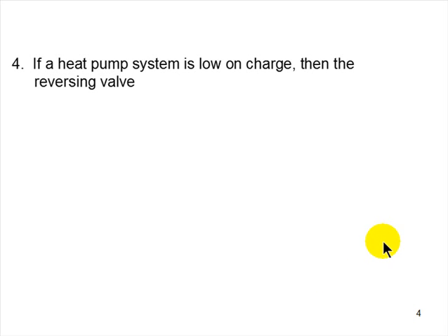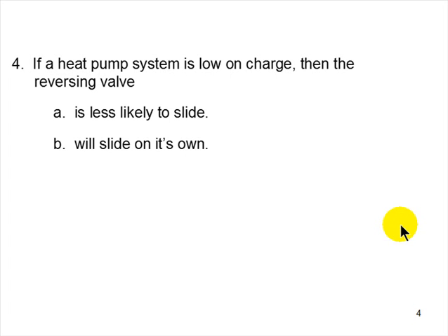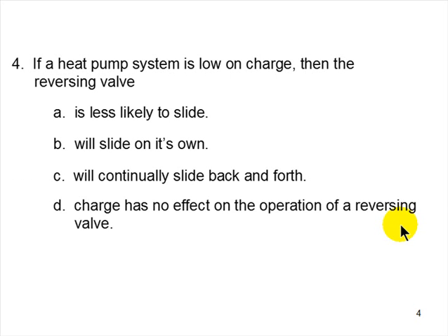Four, if a heat pump system is low on charge, then a reversing valve is less likely to slide, will slide on its own, will continually slide back and forth, or charge has no effect on the operation of a reversing valve. What's your pleasure here? Yeah, if you're low on charge, it's less likely to slide. You've got to have the pressure it takes to push that slide across that Teflon.